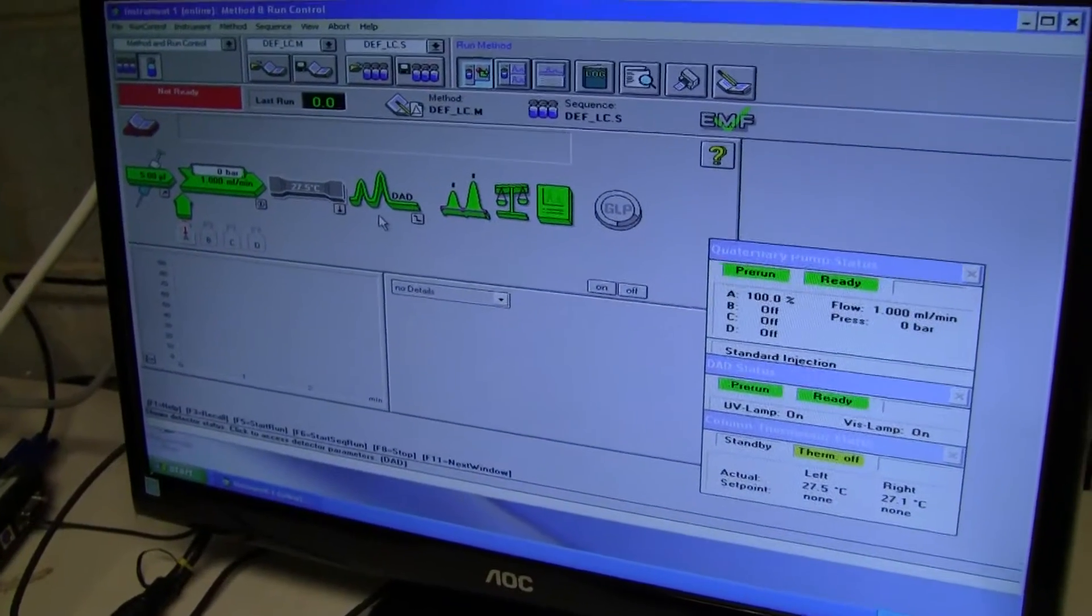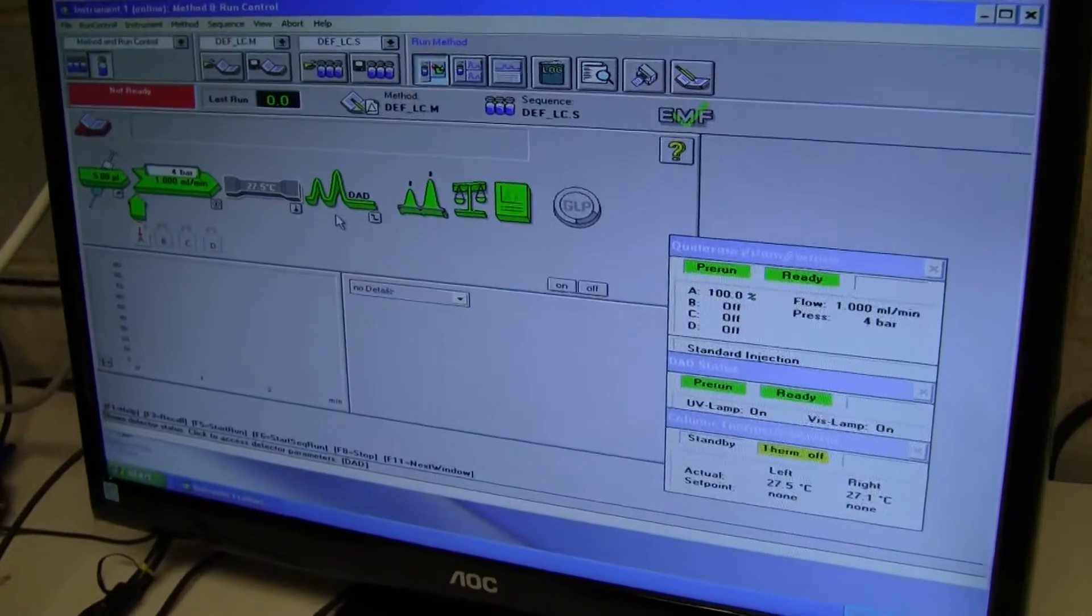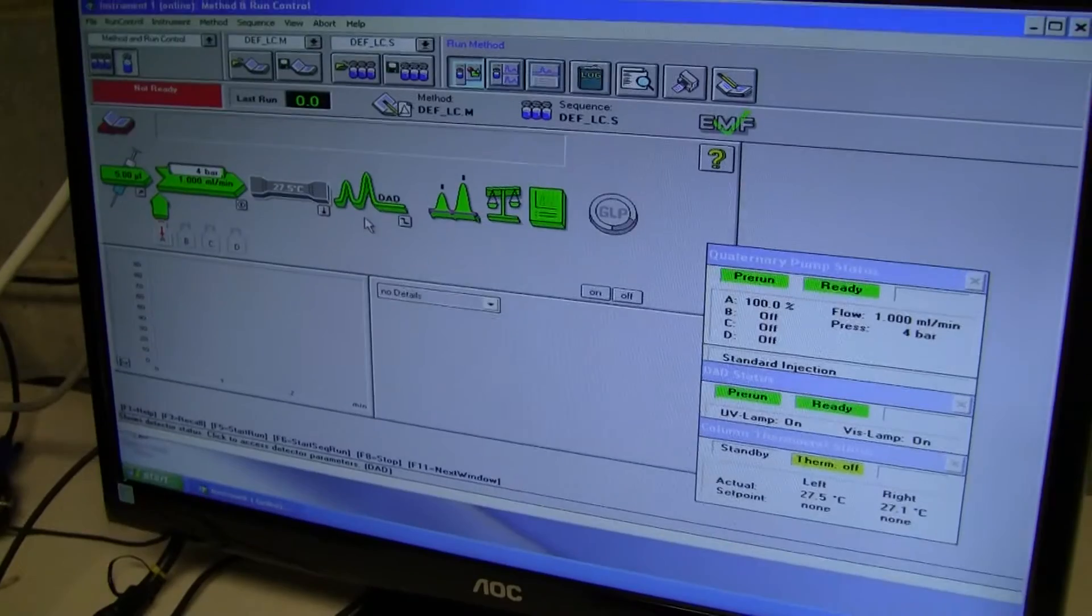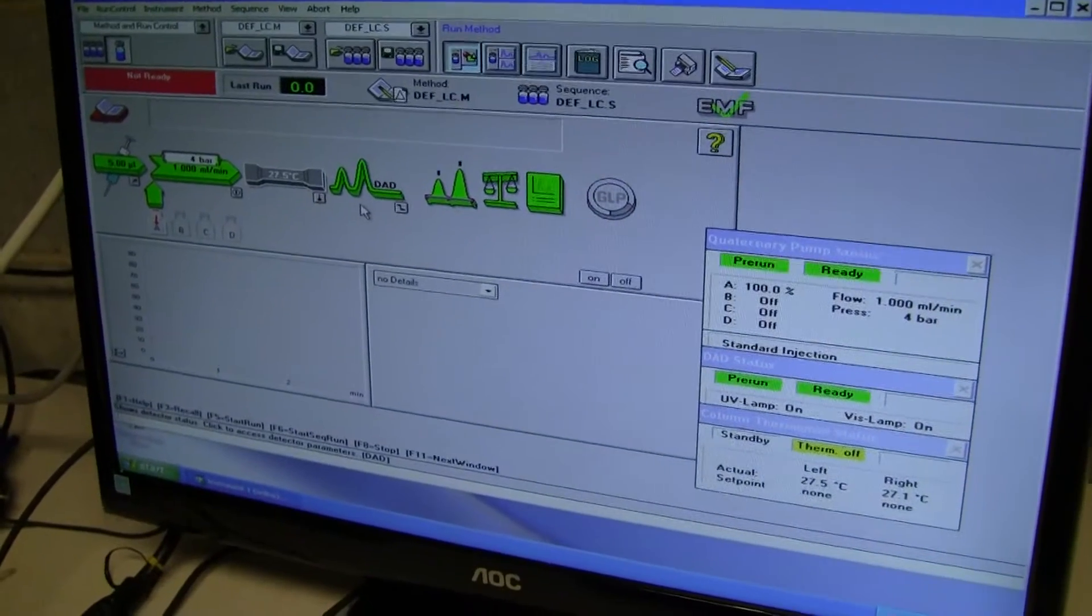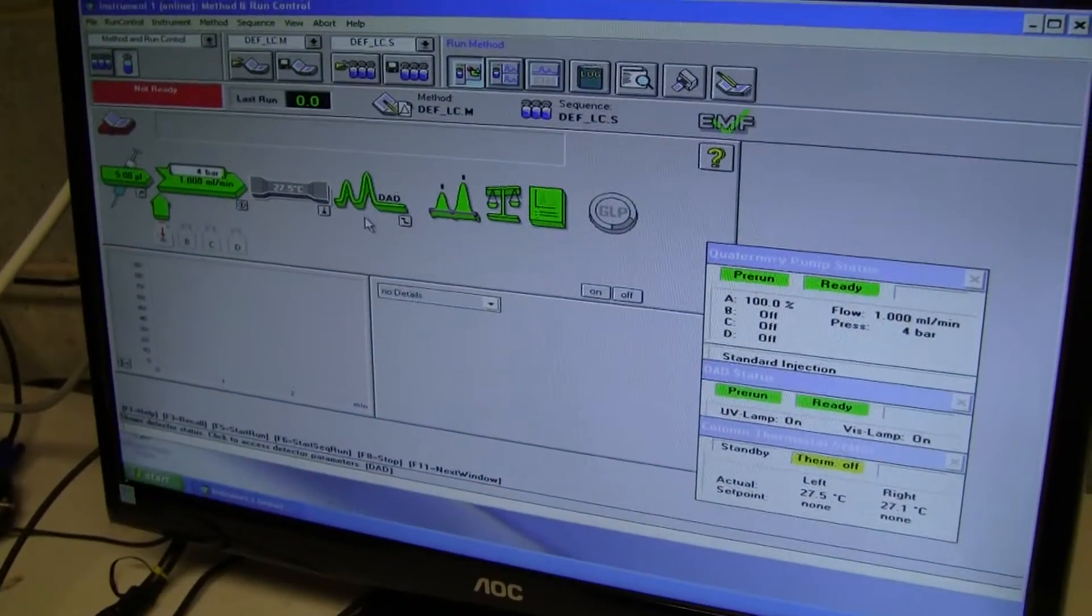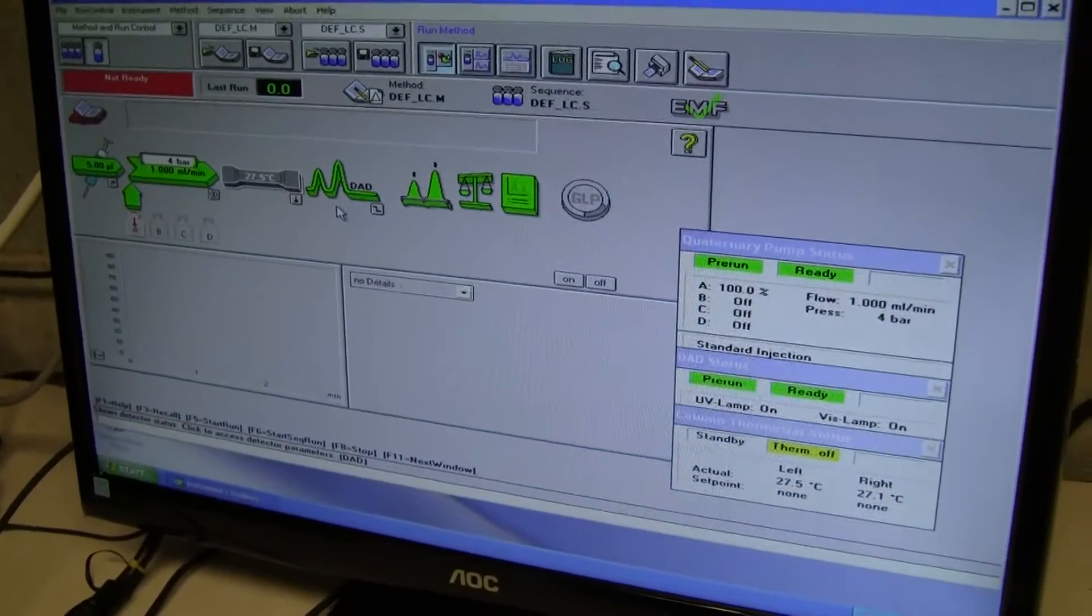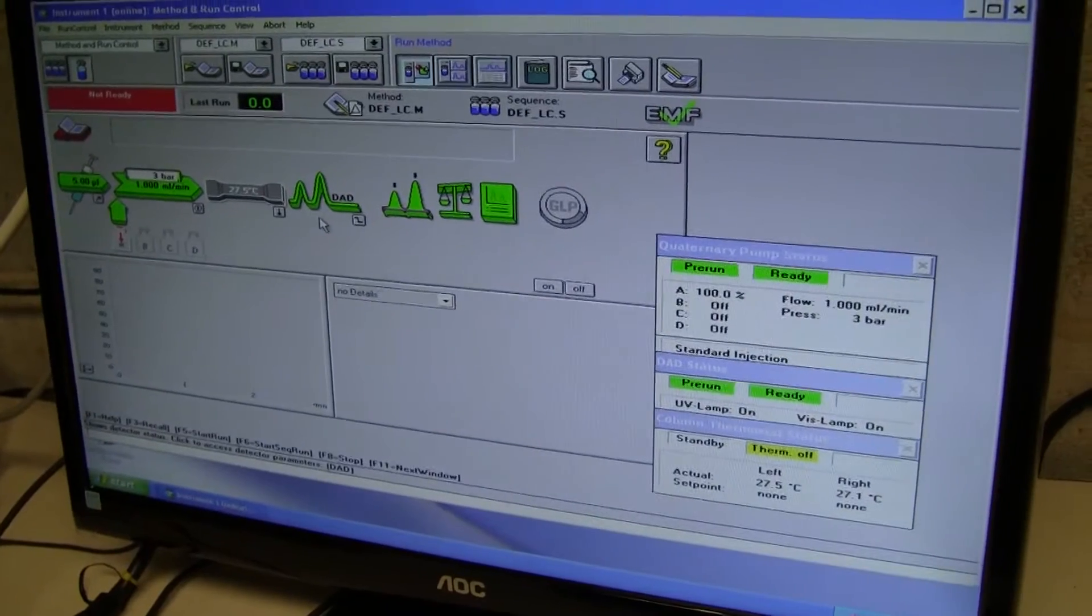No restrictions in the line, zero bar. The DAD detector is seeing all the components. The column heater is not on, although it is reading temperature, so we have good communication throughout.